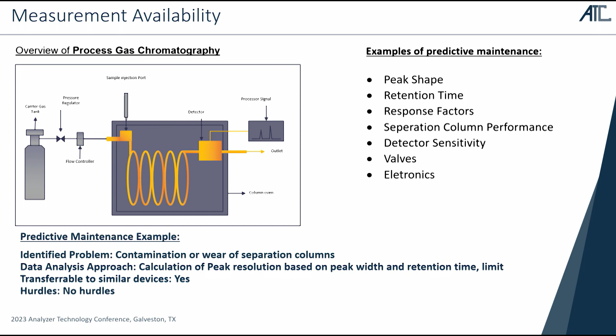So what we have done here is to measure the peak resolution, which is the relationship of how far the peaks are from each other. If they start to come closer to each other and start to overlap to a specific degree, then it's getting critical for your gas chromatograph in the end. So we measure this peak resolution, and if it is violated or going down a bit, we inform the user that he has either a contamination of the separation column or the separation column has a wear process. So it's also easily transferable. You just need a basic understanding of gas chromatography for that.